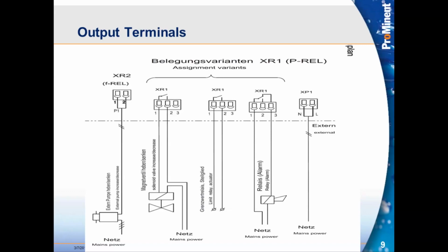Then finally, the third option there is the relay, where we're using it for alarm, and that alarm could be closing or opening. You see that it's sort of, in a sense, I think they refer to that as form C. So we have a common one pole that's normally open, and then one that's normally closed to that common. And then ultimately our power again on the far right.